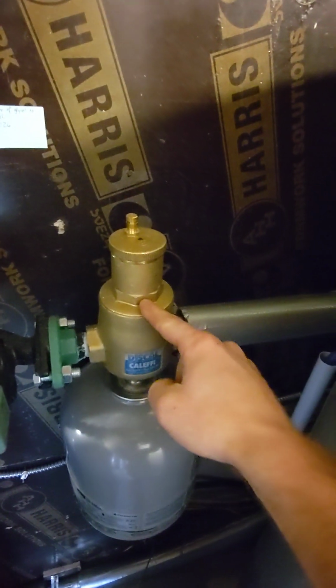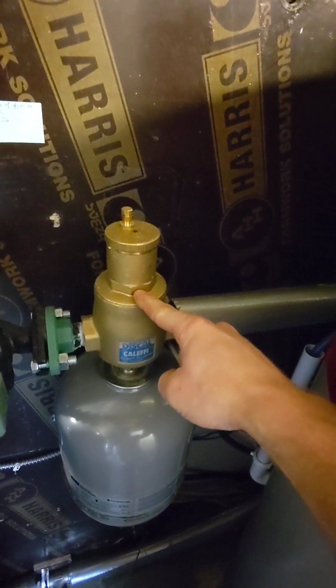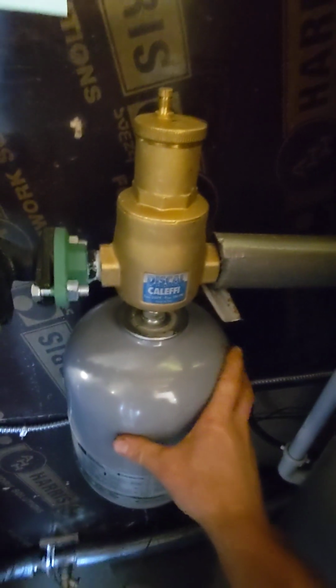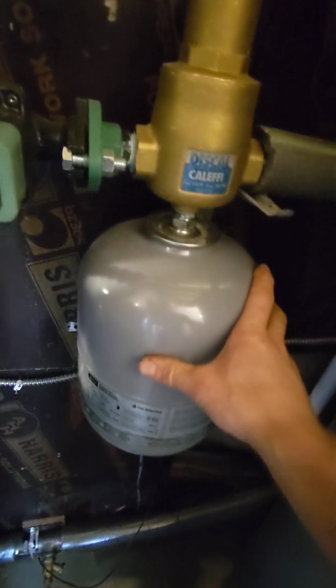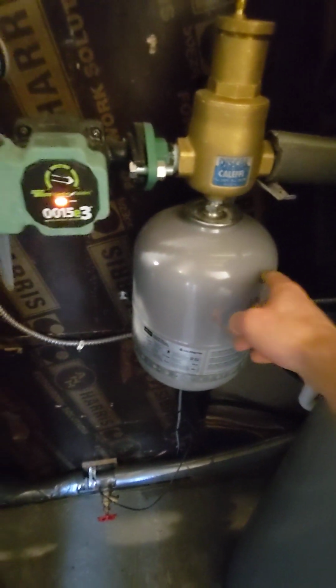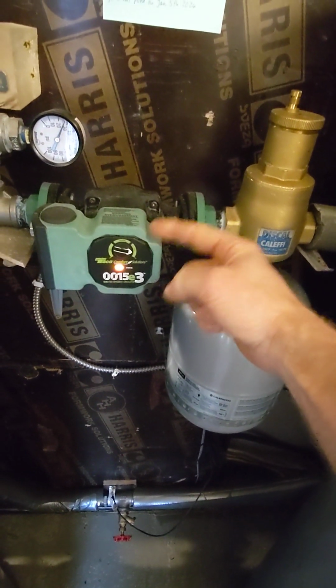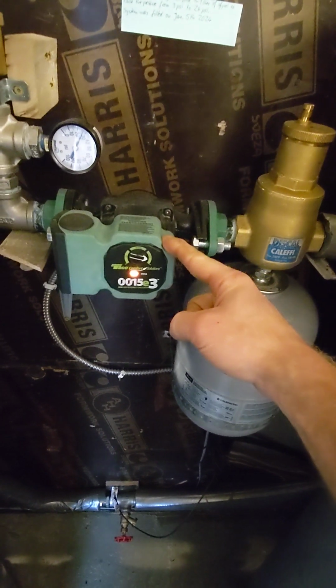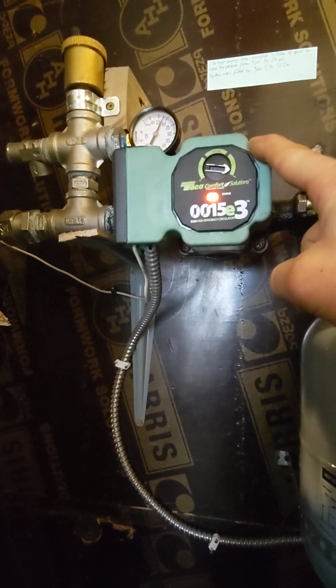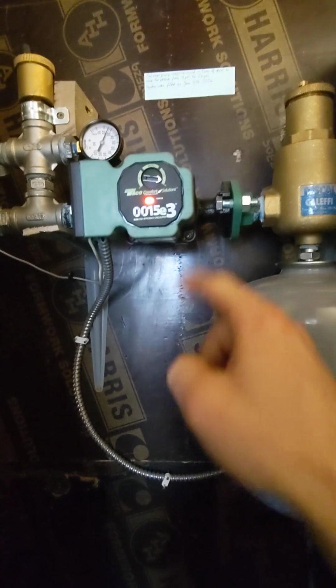So my 1-inch PEX lines coming from the heat pump are entering the house right here. Fluid is being pumped this way, first into the Caleffi air separator valve that I'm really happy with. Then we have the expansion tank to accommodate the thermal expansion as you heat up the fluid. Then it goes into the circulator pump. The circulator pump is moving the fluid around and round between the heat pump and the buffer tank.